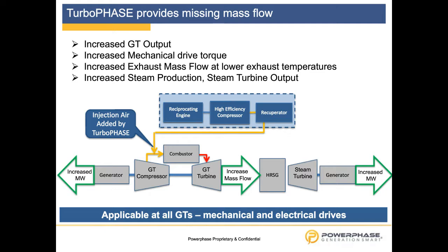With that, we increase directly the output of the gas turbine compressor. And as we have increased the mass flow into the combustion of the gas turbine, the exhaust gas flow will increase as well, giving benefits on the steam cycle. For example, with the increased mass flow, duct burning can be compensated for. It can be switched off, which has another benefit then in terms of fuel savings. With our injection, we are always looking into being below the design capacity of all components and injecting below ISO condition. In case we are going above ISO condition, a comprehensive investigation on site will be done in order to see about the capacity of the steam generator, of the steam turbine generator, and all electrical and mechanical components.